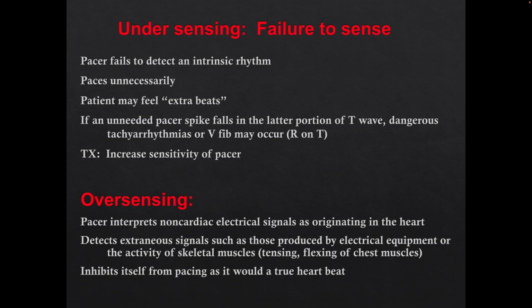You bring that fence down, or the number lower. So I'm going to use a number of, say, 0.05 up to, let's say, 2. 2 is going to be less sensitive, right, because it's a higher number. You bring the number down to 0.5 or 0.05, whatever the case is, you're going to see a lot more. So that's your sensitivity. So if you undersense, you want to increase the sensitivity. So you want to make the number lower. It sounds opposite though. You say, oh, I want to increase it, so you want to increase the number. You don't want to increase the number. You want to bring the number lower. You want to be able to see over that fence and bring it down as low as you can without now oversensing, because that's where that gets tricky.